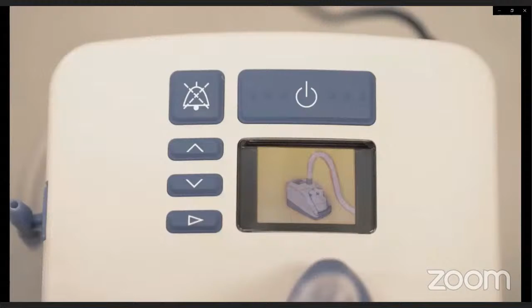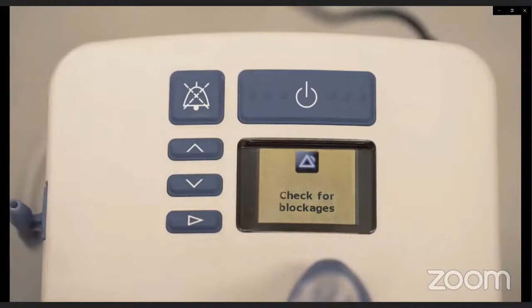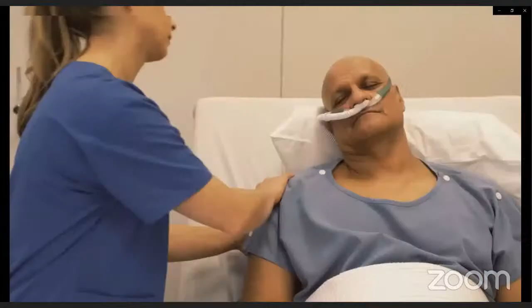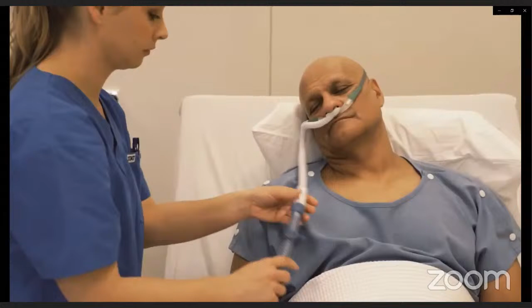The Evo 2 has been designed to be as reliable as possible and will automatically raise an alarm when a problem is detected. The cause of the alarm is shown on the display. Silence the alarm with the mute button. In this example, the alarm was raised because a blockage has been detected. Once the blockage has been found and corrected, the Evo 2 will continue delivering therapy to the patient.